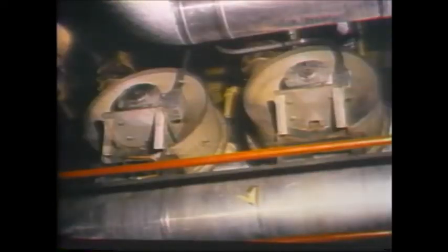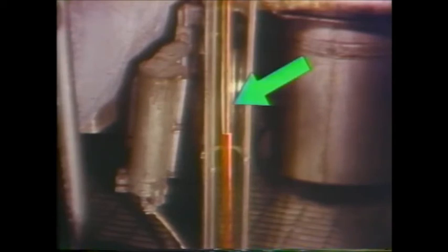The temperature of the cooling water flowing through the gland steam condenser must also be checked. The temperature must be low enough to ensure that condensation is occurring properly. And you also want to make certain that the exhausters are working properly and that there's a vacuum within the condenser. And finally, check that the condensate water level in the gland steam condenser is being maintained at the proper level. There's usually a sight glass that allows you to determine the water level.